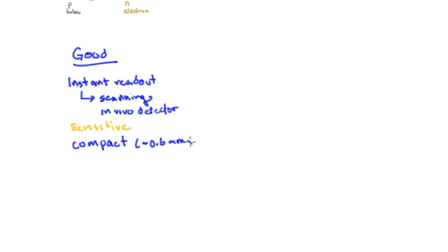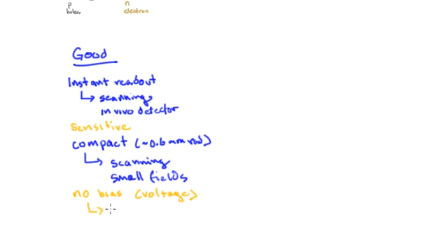They're also compact, with maybe a 0.6 millimeter radius active region. As a result, scanning with them is very accurate—you can look at small fields and get a very good measurement of sharp penumbra. There's no bias voltage applied to these detectors, which is good for in vivo use, and they're very rugged and durable.